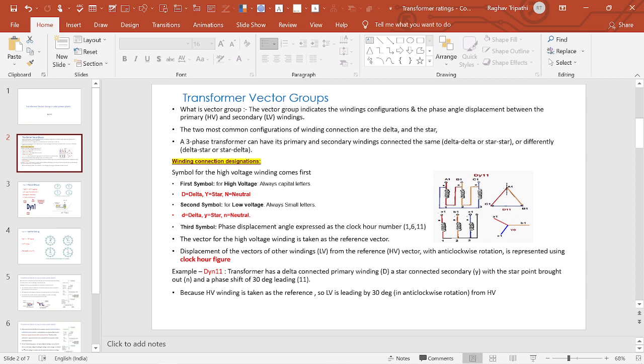Any three-phase transformer can have delta-delta, star-star, delta-star, or star-delta configurations. When representing the winding configurations in a single line diagram, the HV is denoted by capital letters, LV by small letters, and the phase angle displacement is indicated by a numeric value such as 1, 6, or 11.